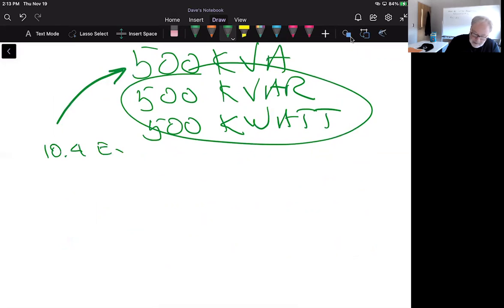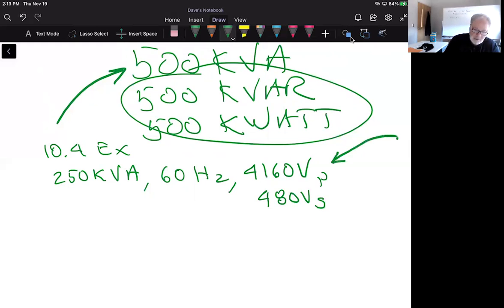So 10-4 example says that I have a nameplate of a distribution transformer and it is 250 kVA. It is 60 Hertz. And on the primary, it's rated at 4,160 volts and on the secondary 480 volts. So what that means, this is the acceptable voltage on the primary side. And then based on the turns ratio, we're going to output on the secondary side of very common voltage of 480 volts. He says, calculate the nominal and primary secondary currents. So that's pretty easy to do.